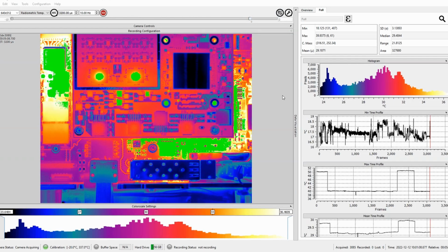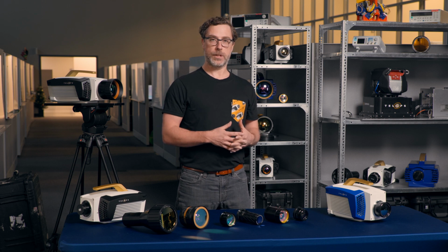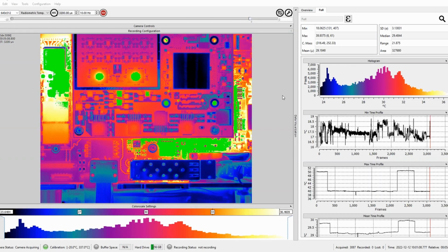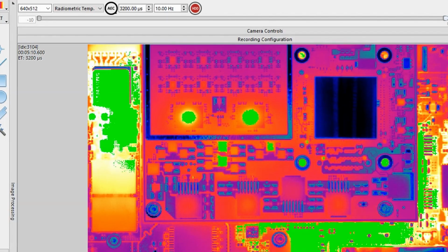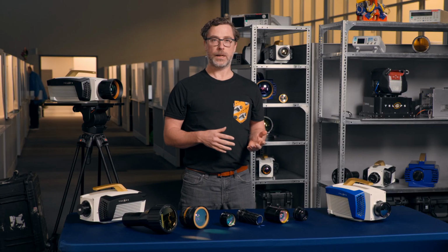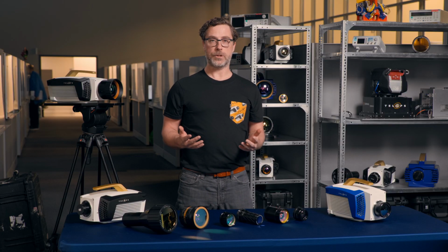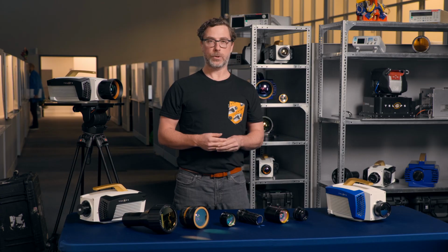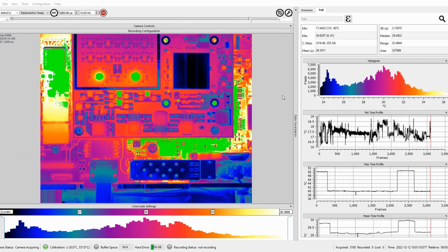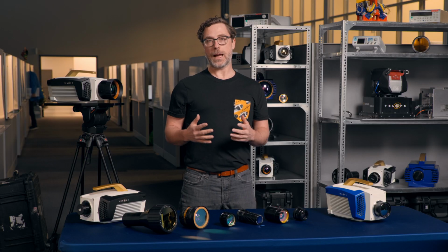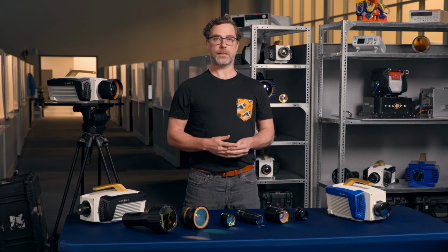A printed circuit board, which is viewed here with our fast M350 camera at a given exposure time. We were able to collect good data off lower temperature regions, but hotter regions show saturation, like you see here in green. Lowering the exposure time enabled us to get rid of this saturation and measure valid temperature. But by the same token, we underexposed the lower temperature regions. Therefore, there's no single exposure time to adequately sample all scene intensities.